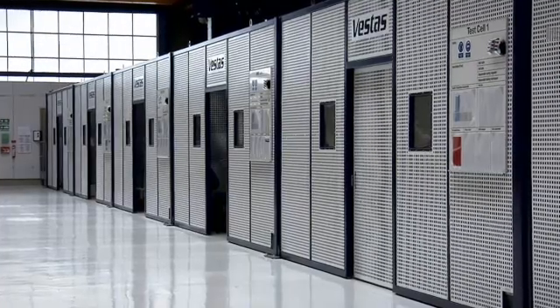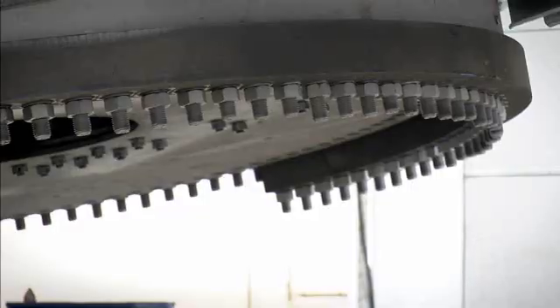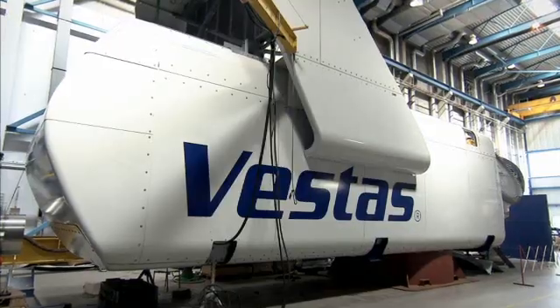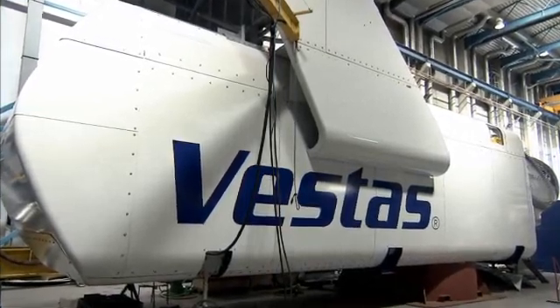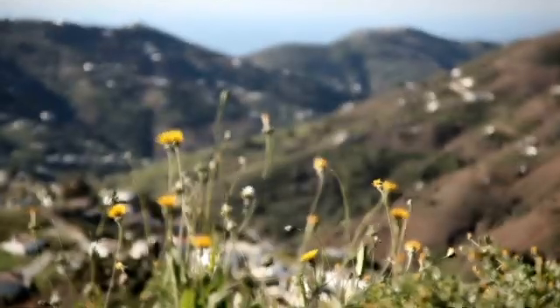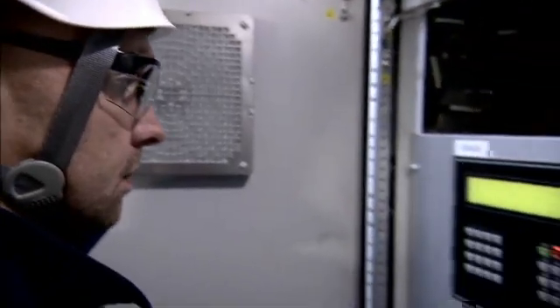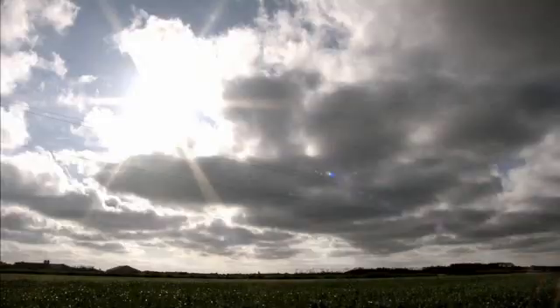The test centre is the only one of its kind able to test complete nacelles using highly accelerated life testing, or HALT, subjecting them to comprehensive stress tests like extreme fluctuations in temperature combined with heavy vibration. The nacelle tested here forms part of the prototype erected at a chosen site in Spain. This site is chosen for its very harsh and severe weather conditions such as heavy turbulence and fast shifting wind directions — especially when combined with other shifting parameters such as humidity and temperature.